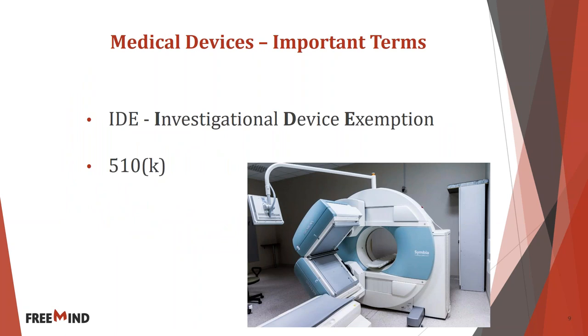Before we dive in and look at some funding opportunities for medical devices, I want to touch upon two important terms that most of you are probably familiar with, but for those who aren't: the first term is IDE, Investigational Device Exemption, which is equivalent to IND for drugs from the FDA. It allows the investigational device to be used in a clinical study in order to collect safety and effectiveness data. So clinical studies, such as pilot and pivotal clinical trials, are most often conducted to support a PMA.